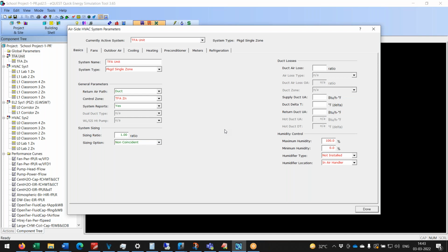So this is how we balance the system. Once we get the tonnage from condenser side, we minus the compressor power, which is in kilowatt, which you can measure using a power meter. That we divide by 3.51 because 3.51 kilowatt is equal to 1 TR as per our calculations. So that way it should be higher, right?